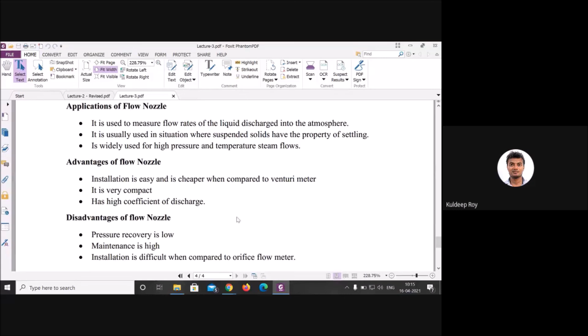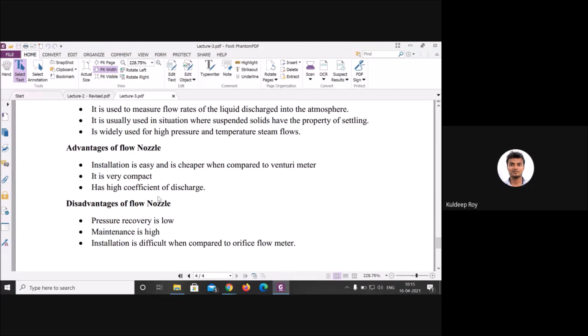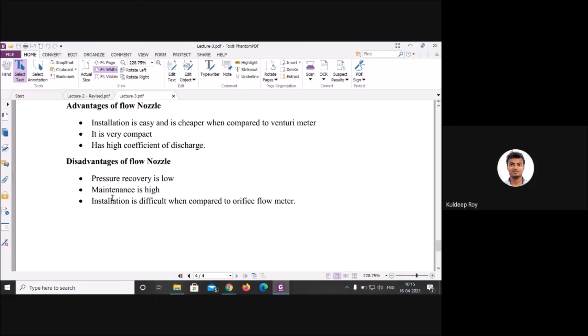Now you can see it is very compact and has a high coefficient of discharge as compared to the orifice, because for the venturi, as I already told, it is near about 0.98, 0.96 like that. But here the discharge coefficient is a little bit lower, though higher than the orifice plate. Disadvantage: the pressure recovery is low, of course it will be. Maintenance is high, but lower than the venturi meter. Installation is difficult when compared to the orifice meter. This is the major disadvantage, because in the orifice you have to do nothing. You make one small hole, apply it in a flowing system, and you can easily determine the velocity and the pressure.